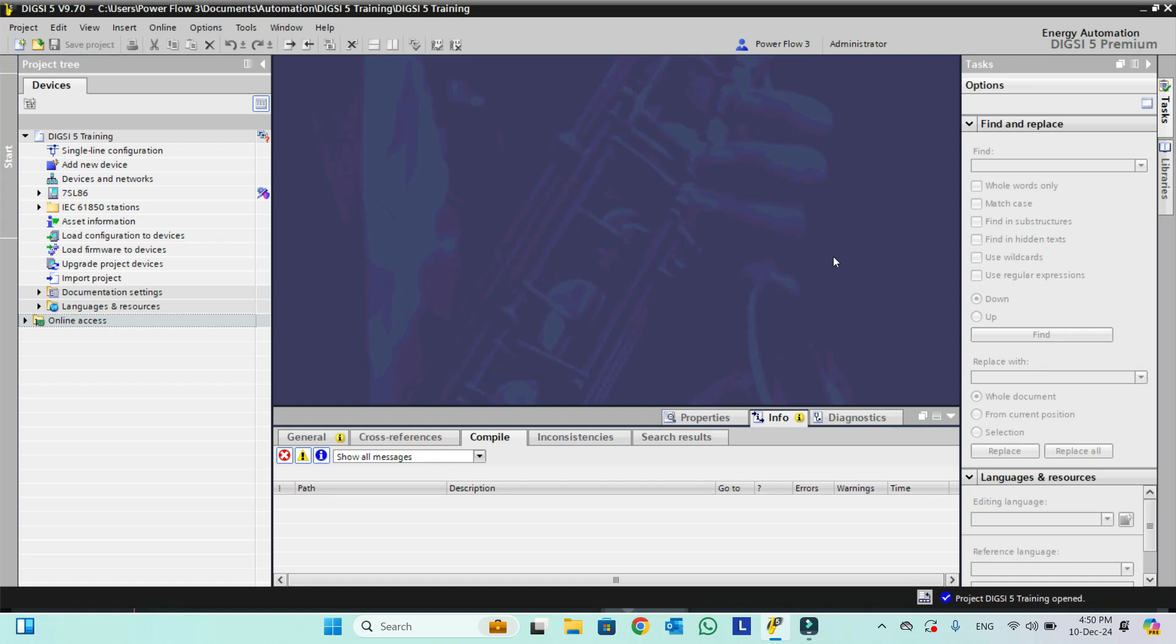Welcome back to DIGSI 5 training course. This is the second lecture. If we have a device in the project tree and we want any driver for it, for example this is the device 7SL86, and we don't have its device driver, how can we get the device driver for this specific device?